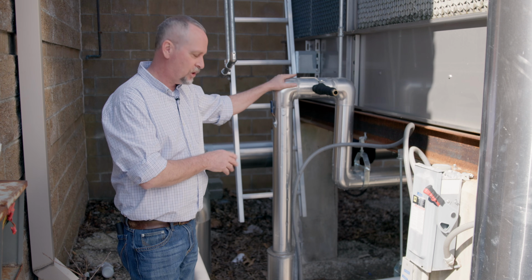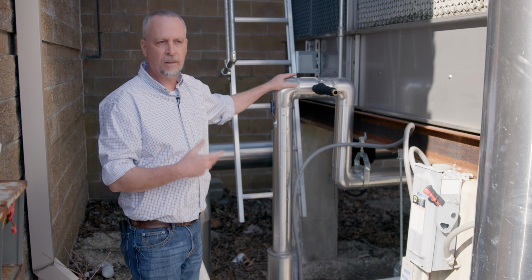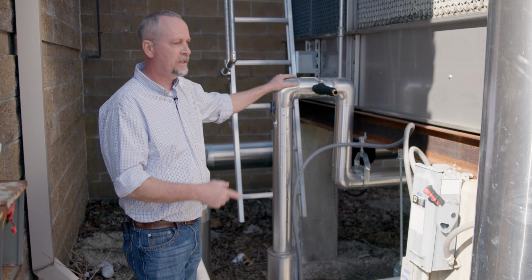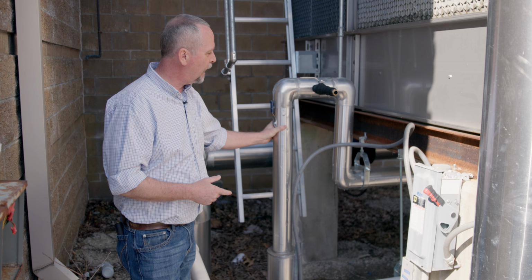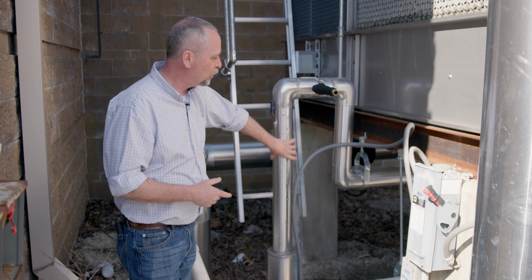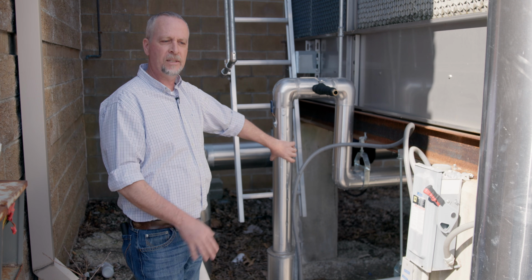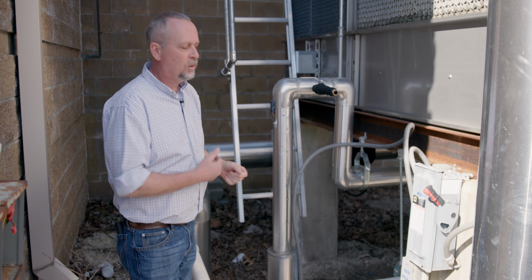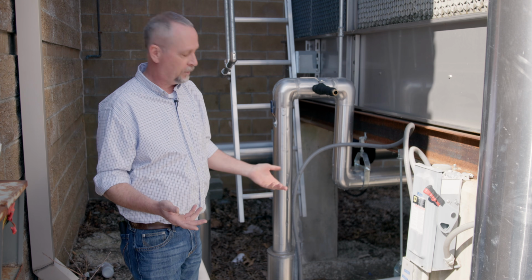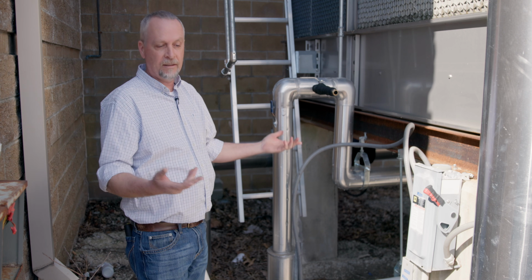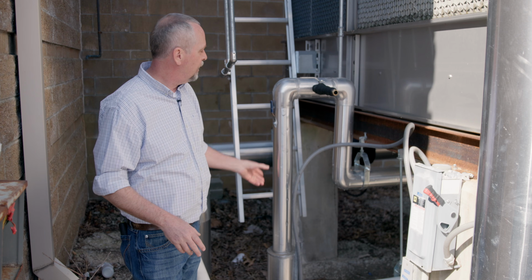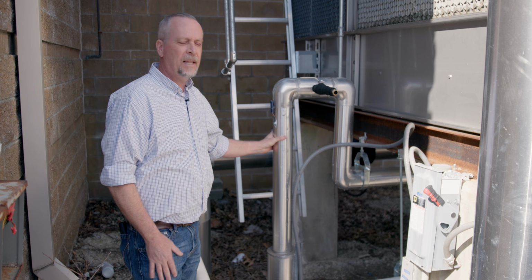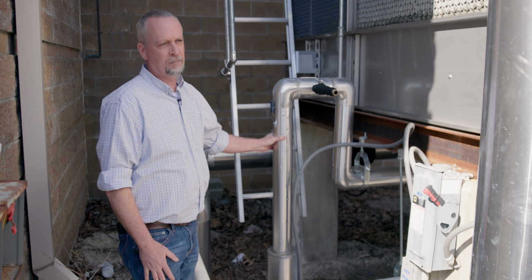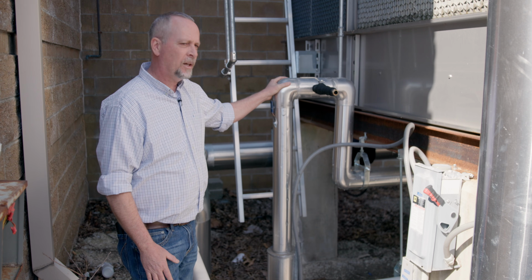This is field installed and it's called heat trace. Some of you may or may not be familiar with heat trace. It's basically an insulated wire that you wrap around the pipe before you insulate this pipe. It'll be set up on a thermostat and it will come on if the ambient temperature gets below the desired setting you put the dial at, typically at least 35. And all that's doing is keeping that pipe warm under the insulation, because the water is not always flowing.